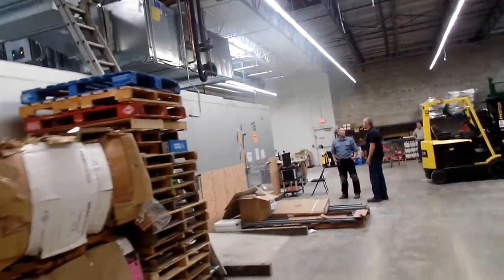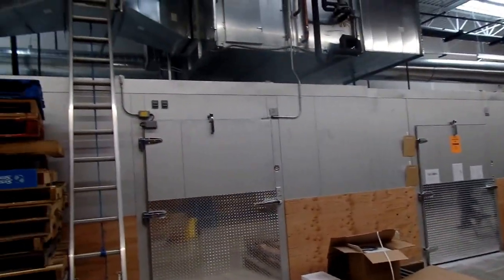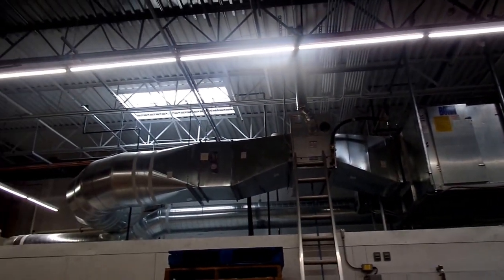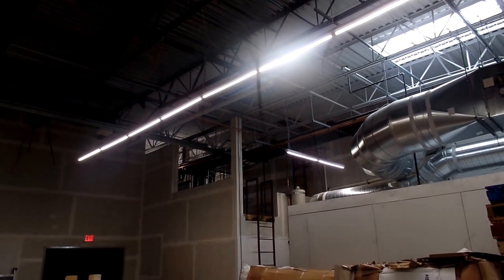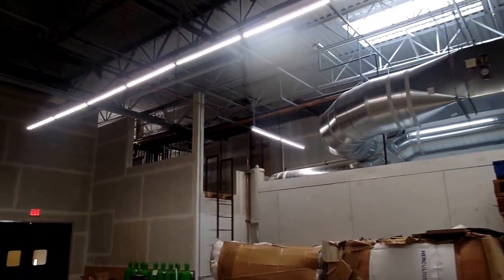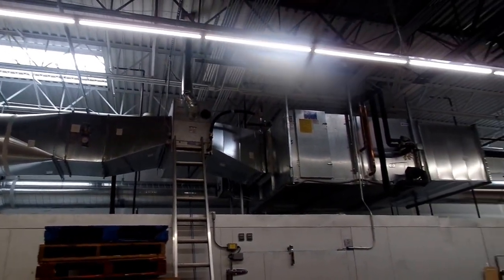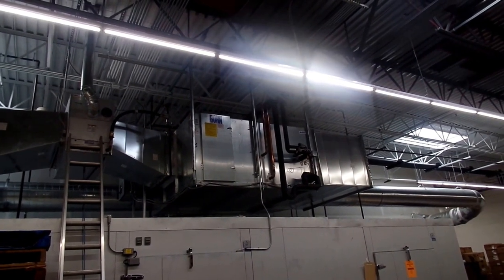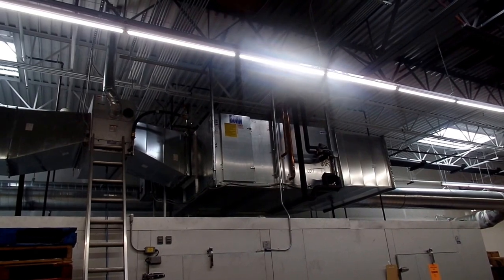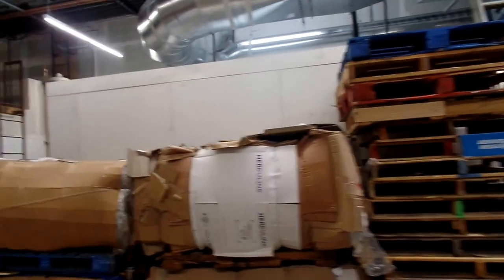The source team is here checking everything out — a whole team of people making sure everything is tuned up correctly. This is our central air handler unit versus four air conditioners on the roof. There's our refrigeration rack up there. We eliminated the machine room, saving that cost, and just have a rack up there. We have gas heat as stage two, plus air conditioning. We're using waste heat off the refrigeration to heat and dehumidify the store. Natural finishes on the cooler boxes versus painted — no need for the paint.